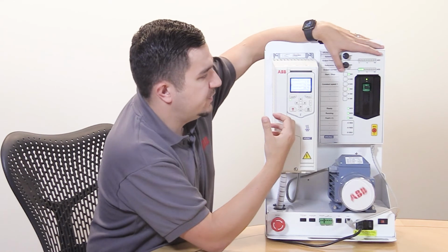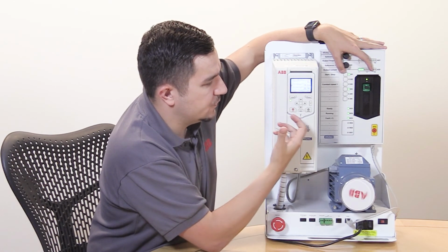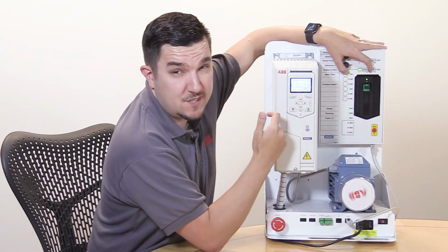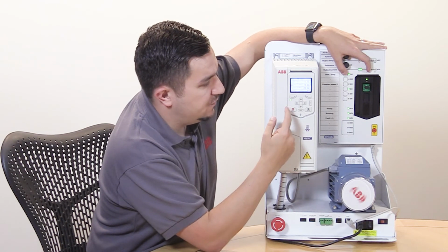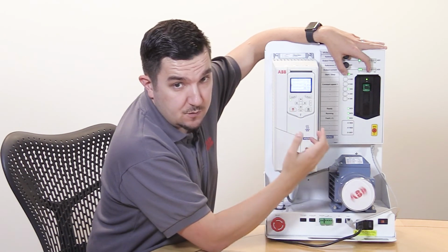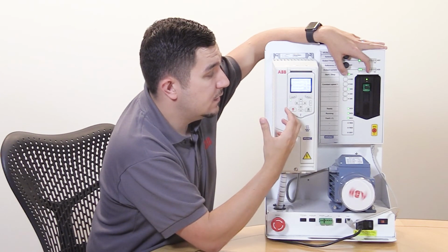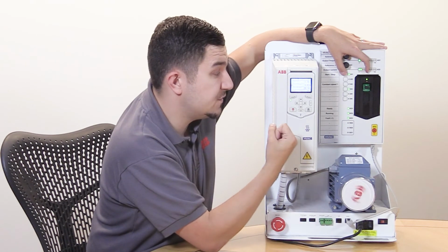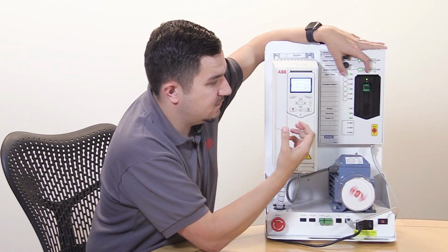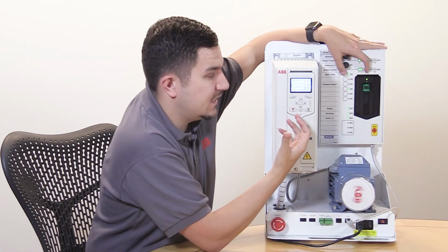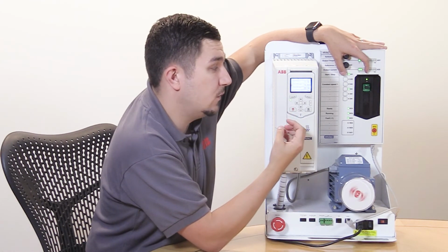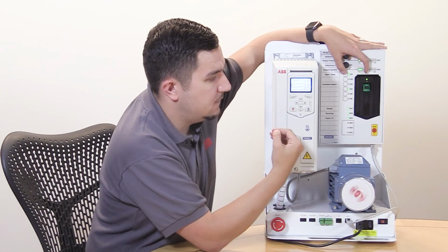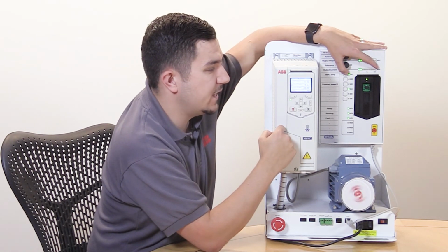One of the additional features behind this, which doesn't show on the wizard itself but when you go through the list, is what we call a sleep mode. What happens is that if we get to that scenario where the motor comes to a standstill, after a certain period of time the drive itself will stop, so it's not modulating. It's a good form of saving energy, and it will effectively do what you tend to do when you go to sleep, in that it'll have some form of wake sequence. So it'll have some sort of trigger, so that if it gets too far to a low point or a high point, it will wake up and kickstart that again.